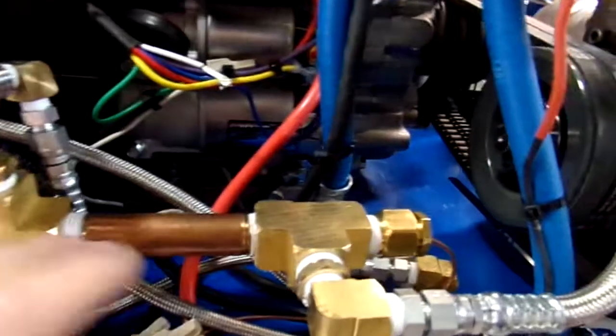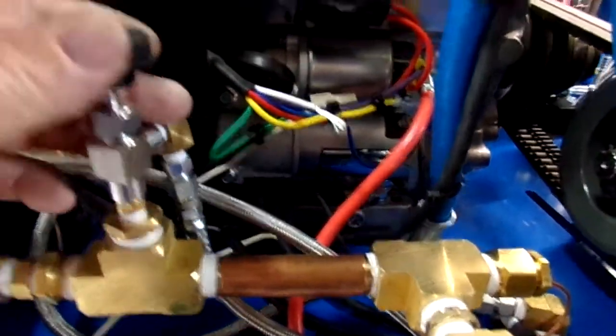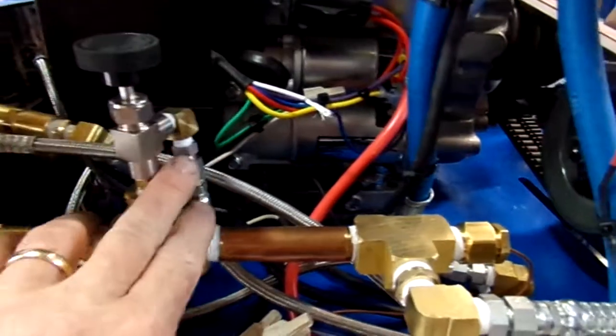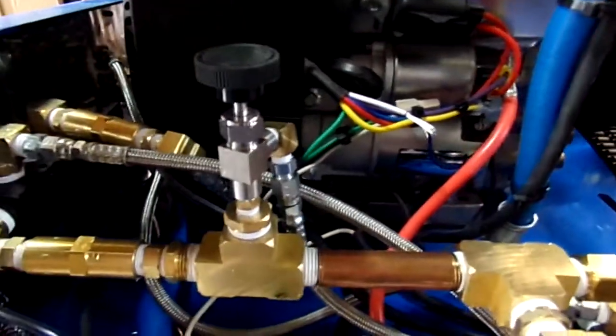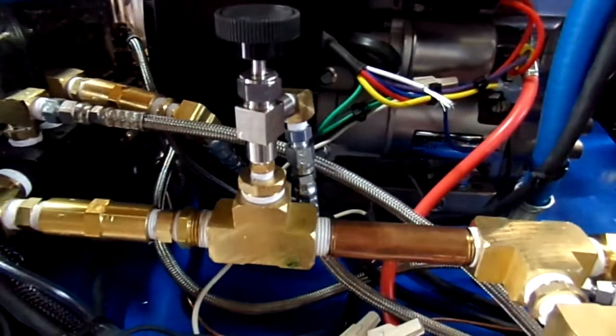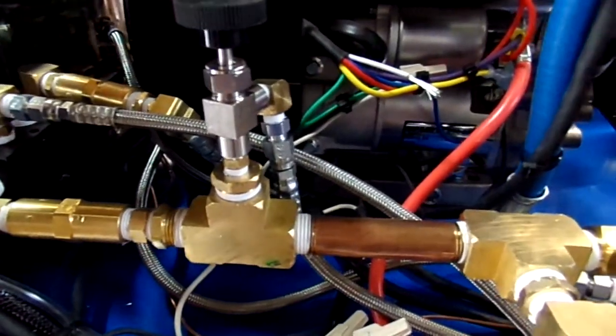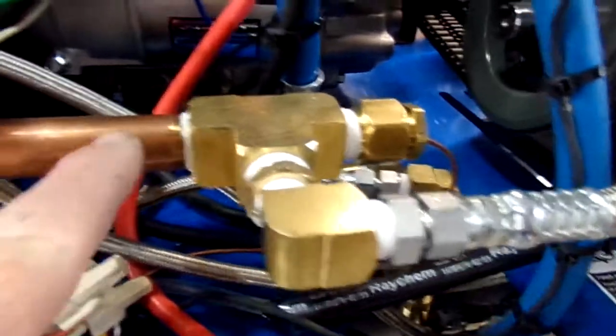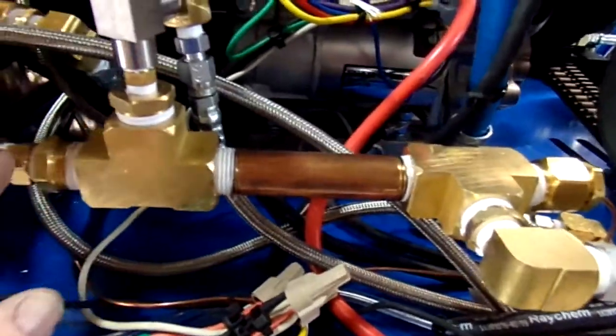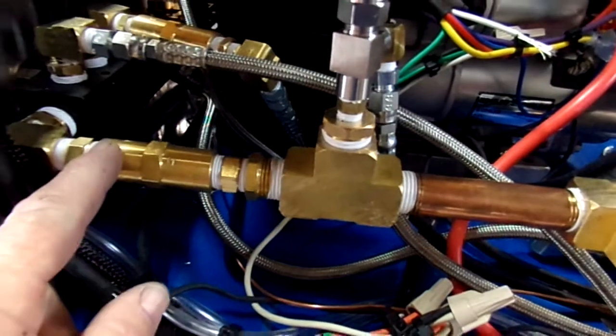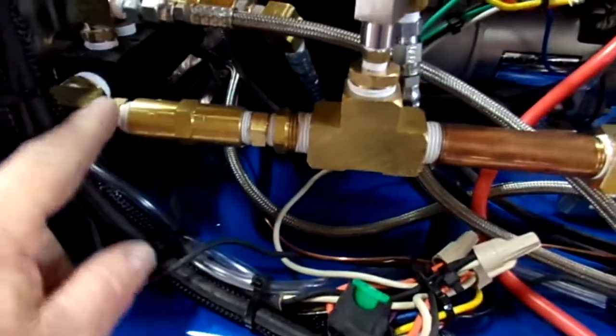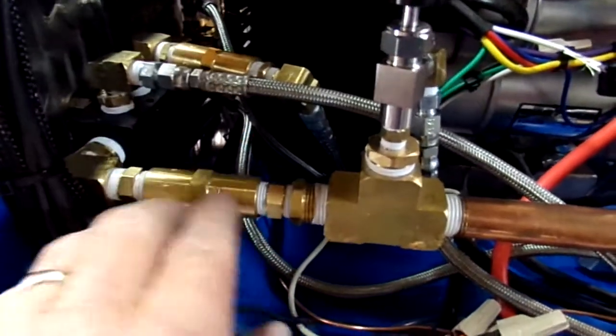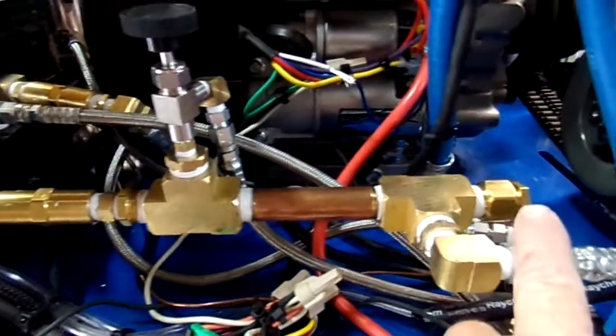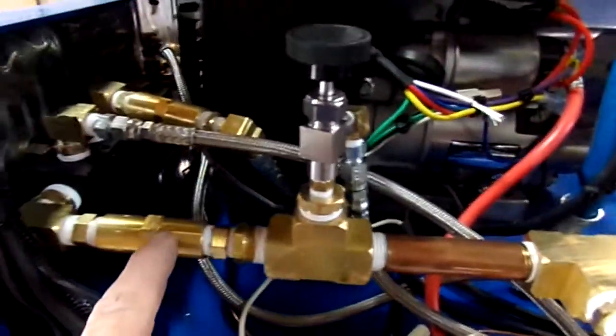So as you can see, as the water flows in this direction, some of it will be bled off by the use of a needle valve, and it'll go into your water box, or it can go into a wastewater tank or water box or a freshwater tank. So anyways, as it comes through here, it comes straight out this way. This is your high pressured line, and basically we use another check valve in order to isolate the injection system of your last step injection for your chemical so that there's no reversal. The key is to keep everything in a unidirectional fashion.